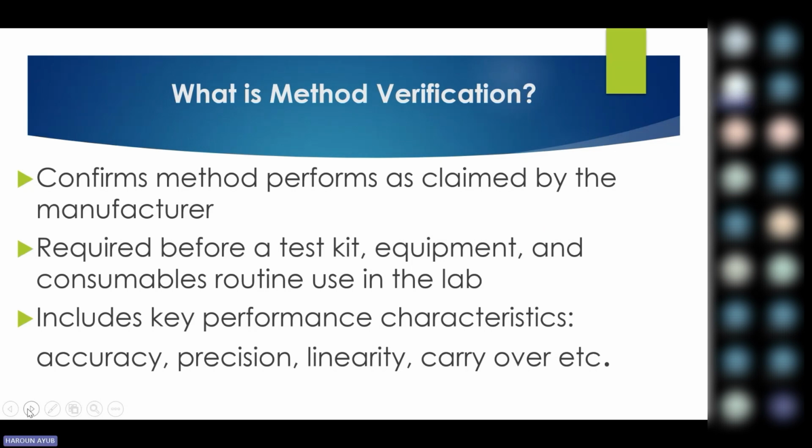So method verification confirms methods perform as claimed by the manufacturer. Once you've received your equipment, or your kit, or your test tubes, perform a method verification process. A manufacturer will do a validation of their equipment, so you come in and do a verification as per their claims.